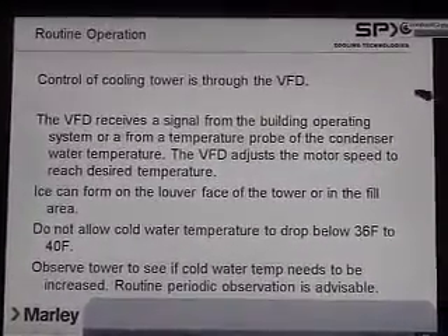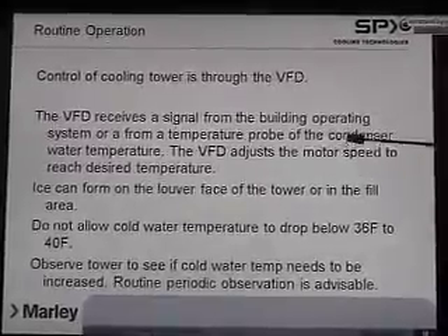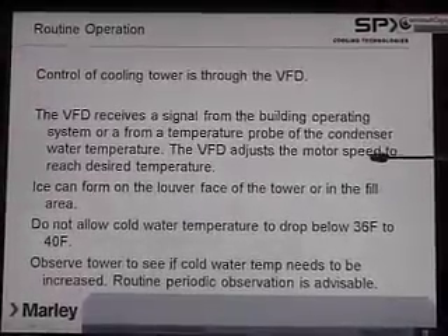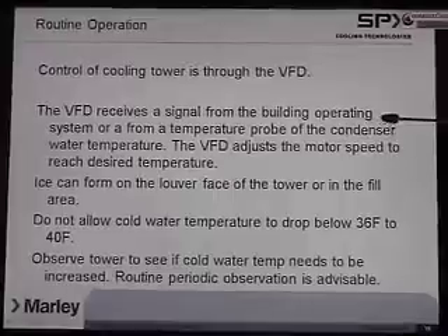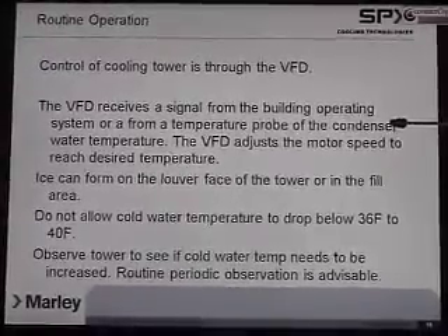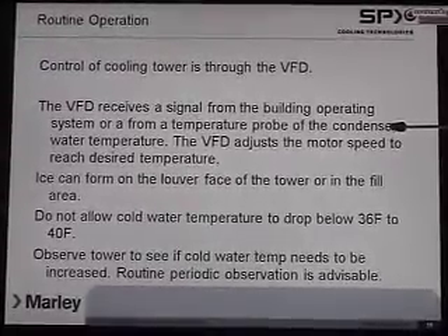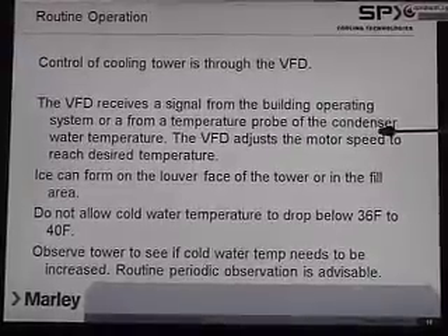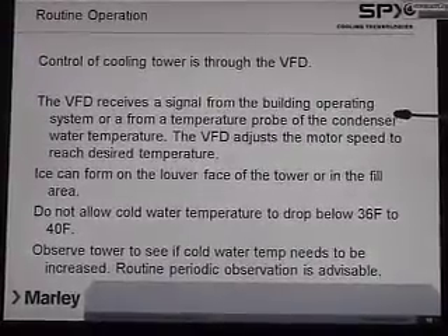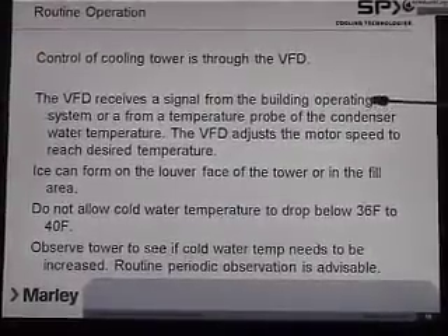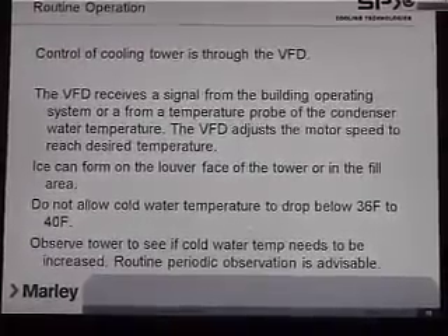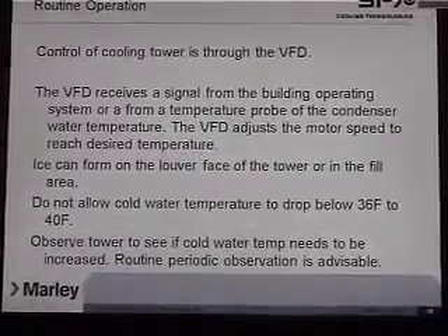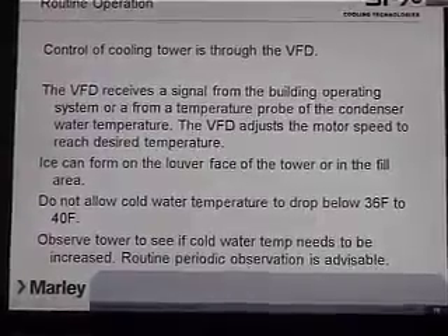Again, control of the cooling towers is through the VFD. The VFD receives a signal either from the building, or sometimes we use a remote thermocouple in the condenser water to determine what the condenser water temperature is. Then that signal goes back to the VFD and it tells the motor to slow down or speed up to get the desired set point on the cold water.